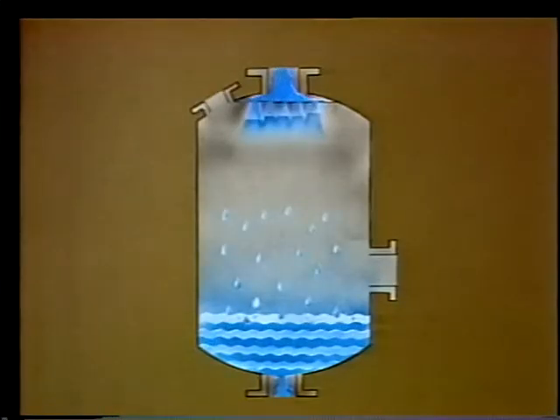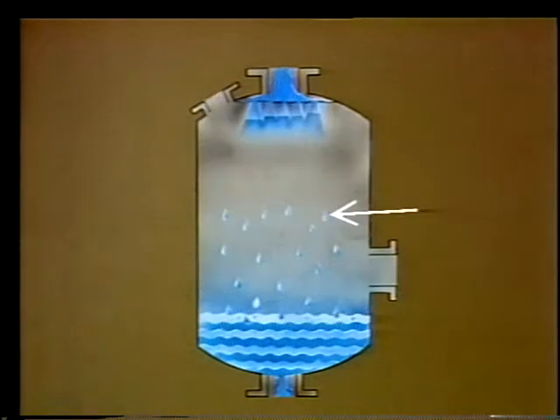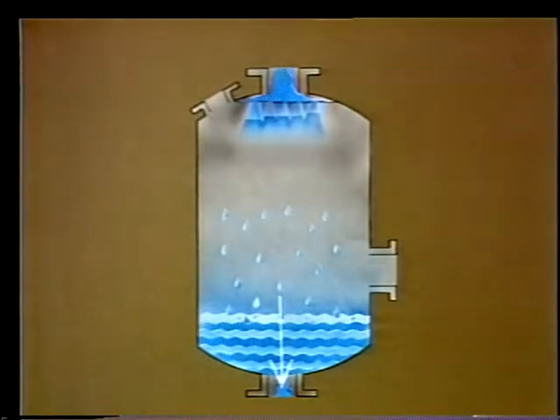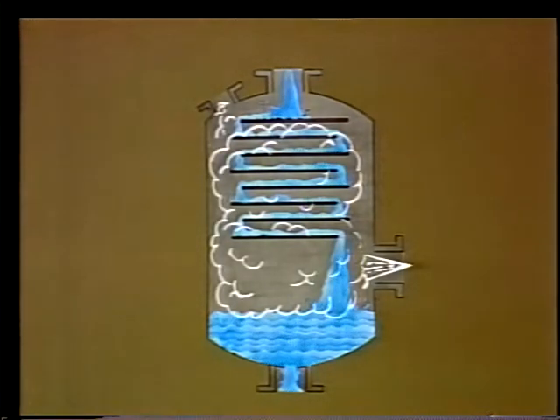The first kind has spray nozzles which spray incoming feed water down from the top through a rush of steam. This steam heats the falling water spray, condenses into water, and falls to join the feed water as it goes on its way to the boiler. The principle of the second kind is the same but this one has water coming in and cascading over trays like a waterfall. As the water runs down over the trays, it's mixed with the live steam in the shell and gets heated up. At the same time the steam is condensed into water and falls down to join the feed water system.